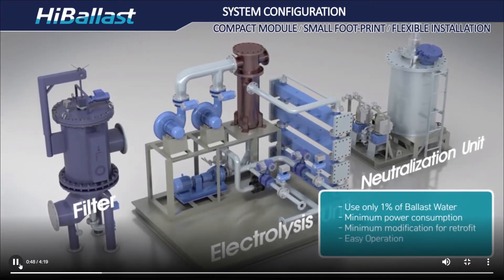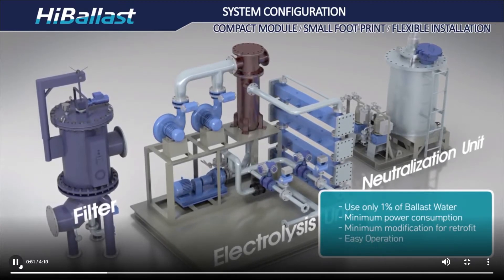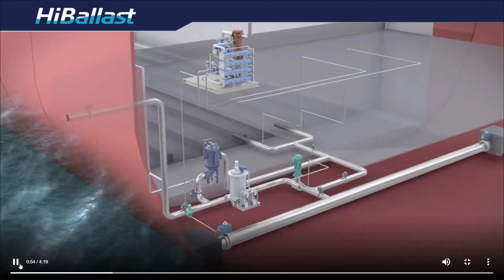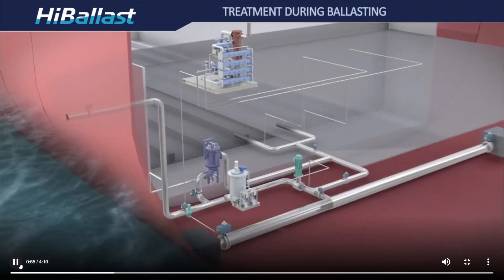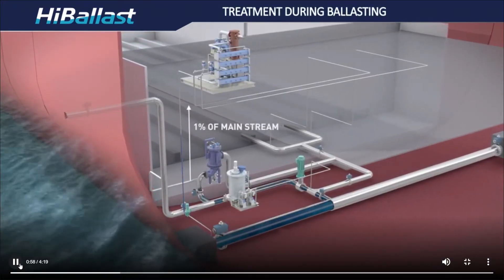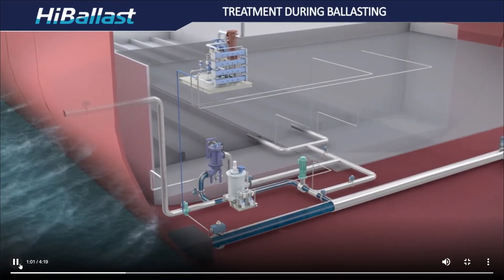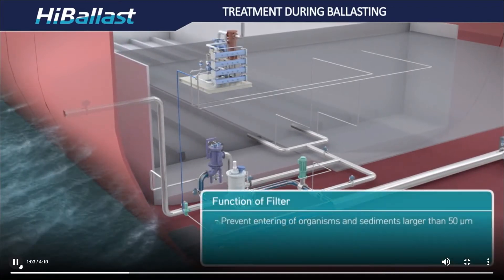A remote control system composed of a Windows-based HMI facilitates easy operation. A filter installed at the ballast pump downstream removes the inflow of sediments or aquatic organisms larger than 50 microns, greatly reducing uncertainty from various local marine environments.